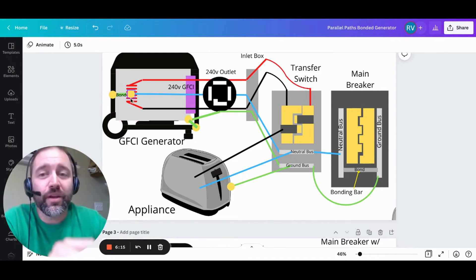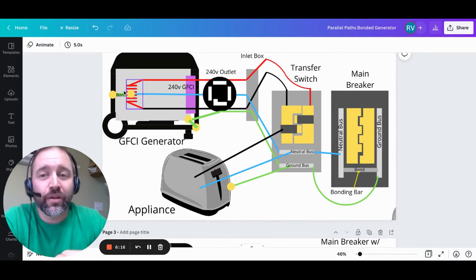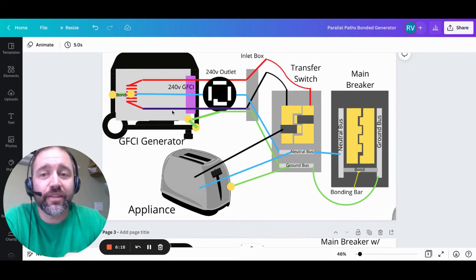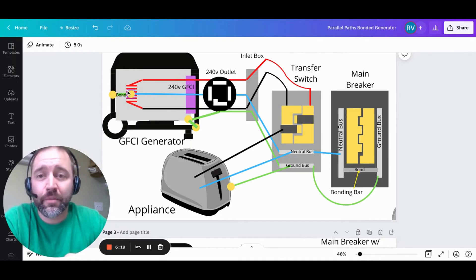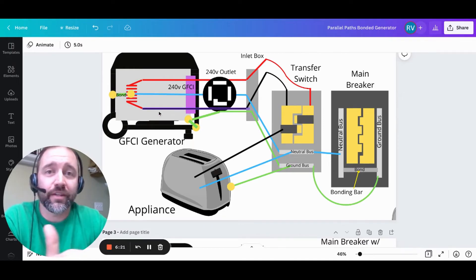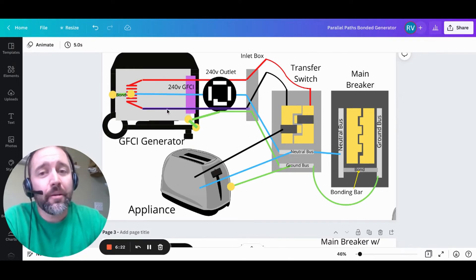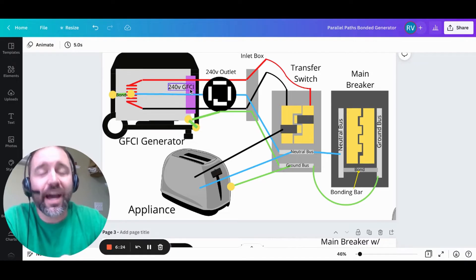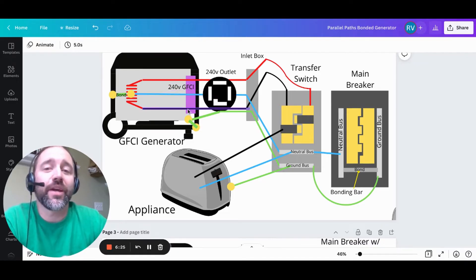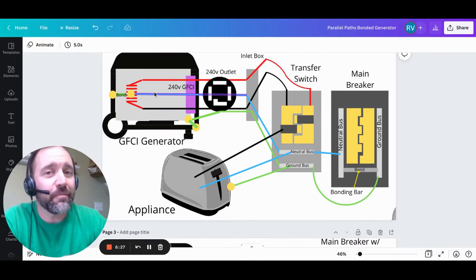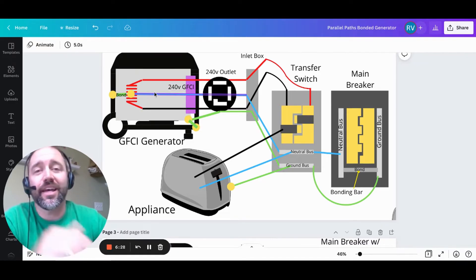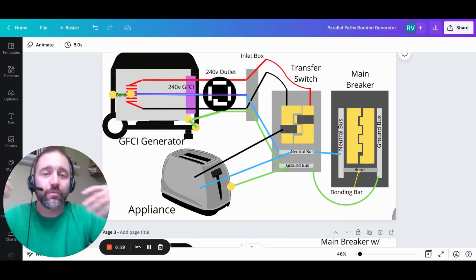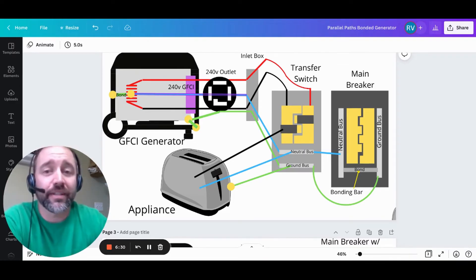So again, at this point, as far as the coils are concerned, we have 7 leaving and 7 coming back. 5 and 2, but 7 coming out here. But as far as the GFCI is concerned, we only have 7 going out and only 5 coming back. It creates that imbalance, and it will trip each and every time.